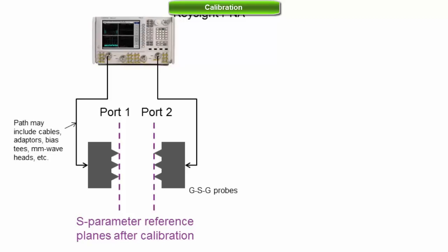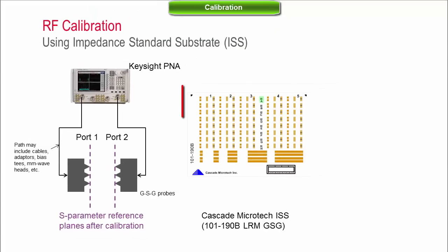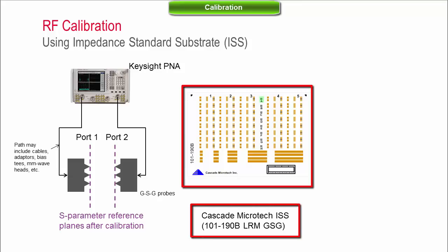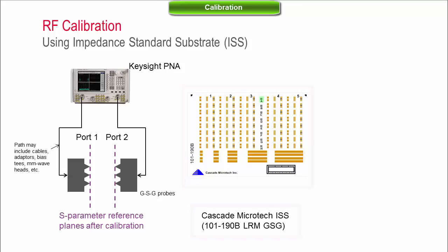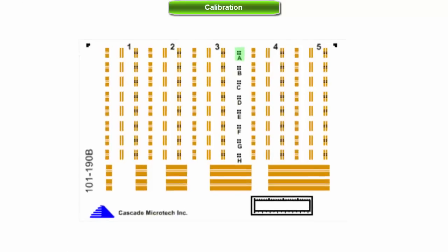In most systems, calibration is done by measuring known standards on a dedicated substrate to compute the correction coefficients. For cascade probes, this substrate is called impedance standard substrate, or ISS, and includes various sets of device standards.